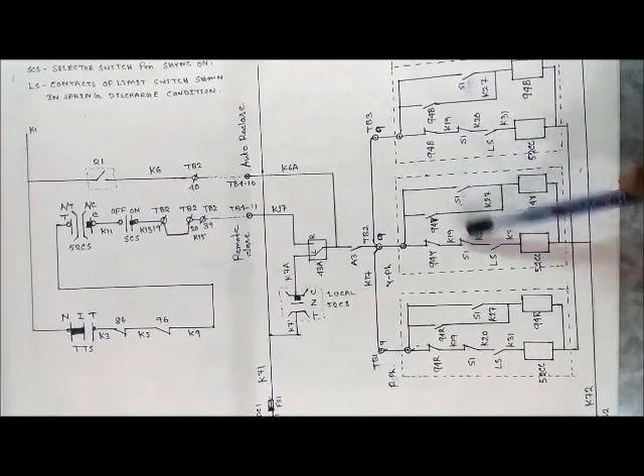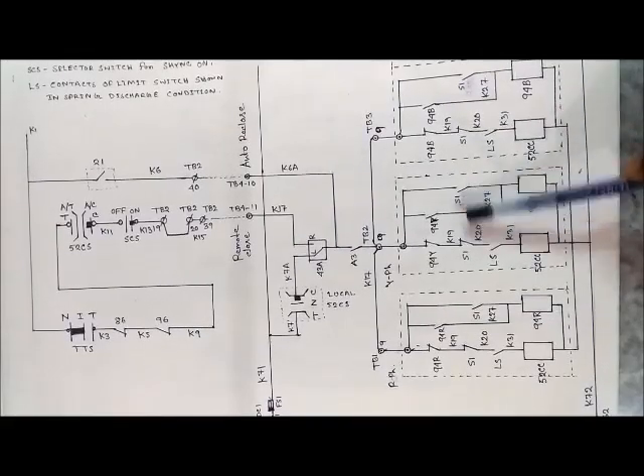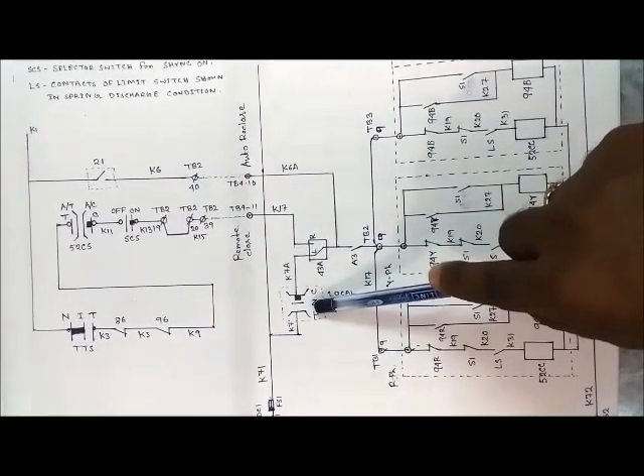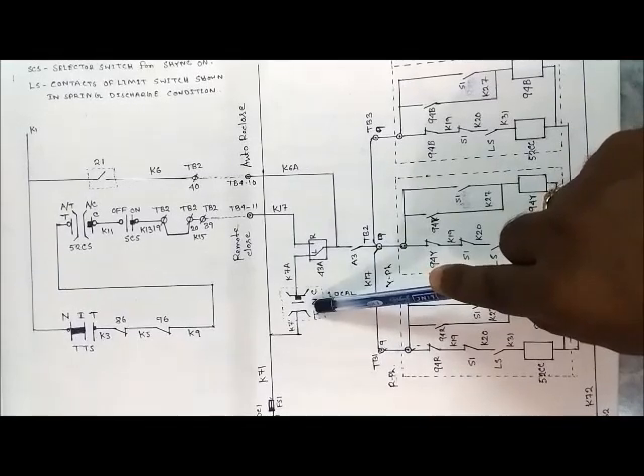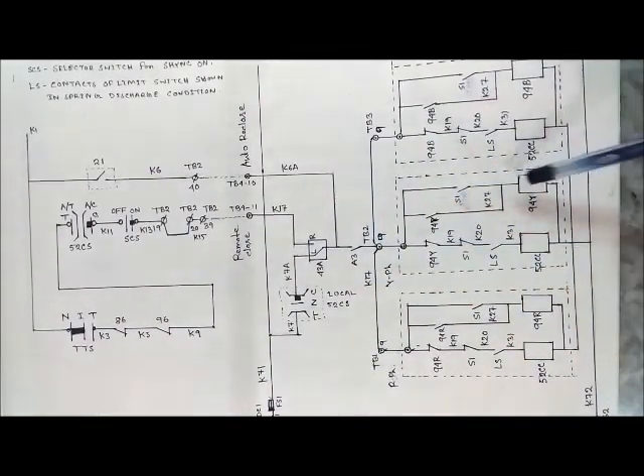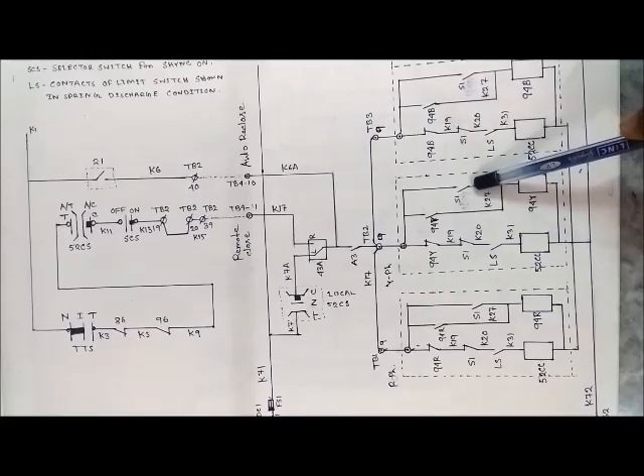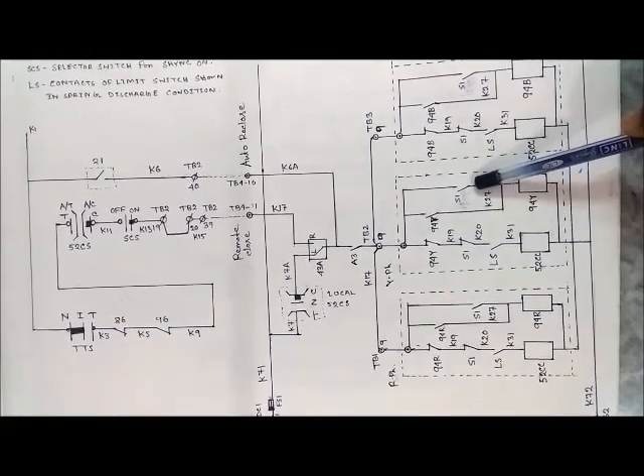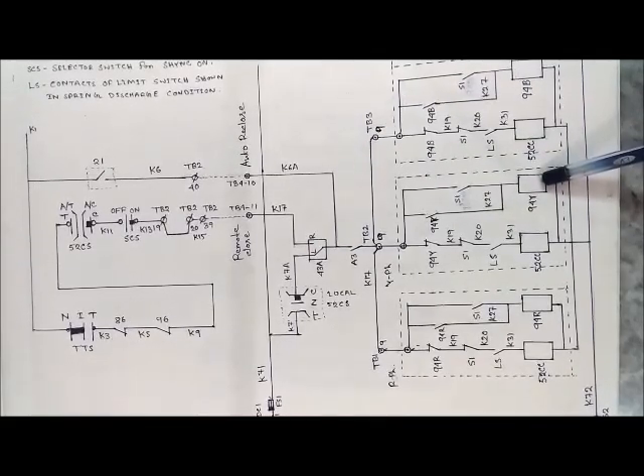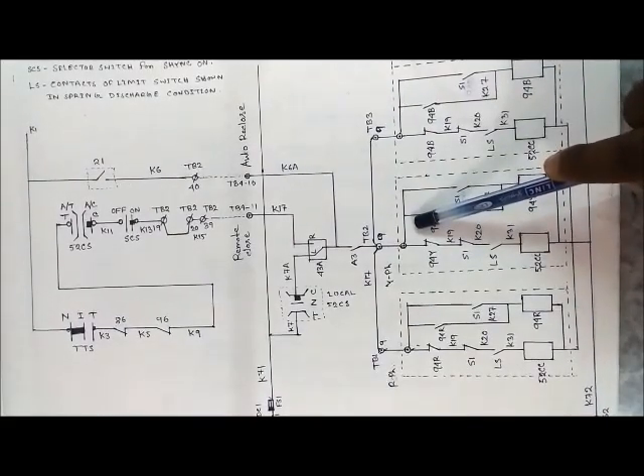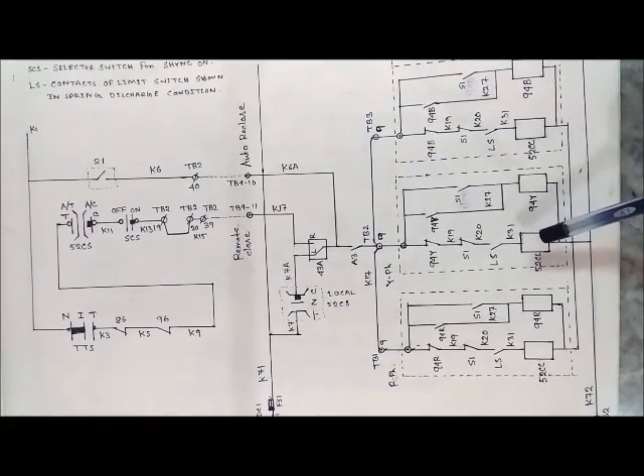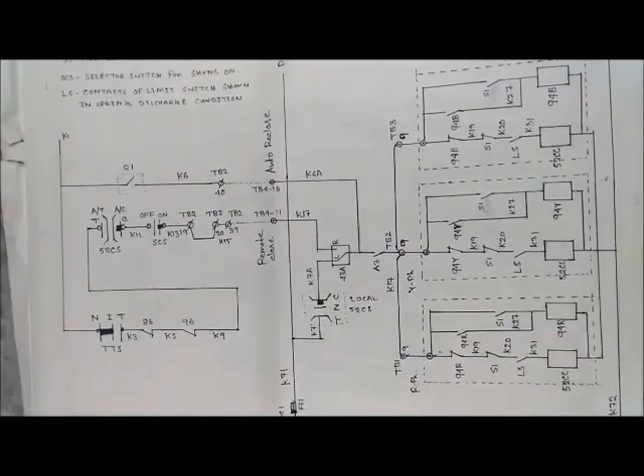As soon as DC passes through the closing coil, the closing coil energizes and the breaker turns ON. The auxiliary contact changes its state — this contact comes to NO position and this contact comes to NC position. If another closing pulse is given, or the control switch is held in the close position, the DC does not reach the closing coil. Instead, it comes to the anti-pumping relay via the auxiliary contact of the circuit breaker, energizing the anti-pumping relay, which latches through its own contact and prevents another closing path to the closing coil. This is the function of the anti-pumping relay.